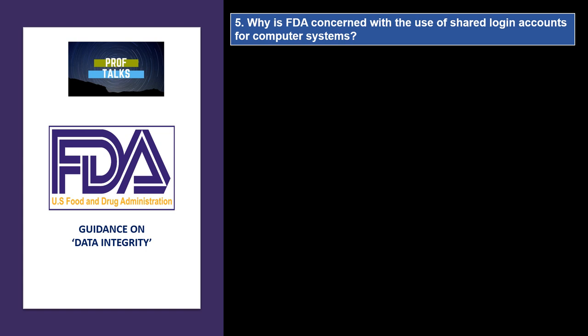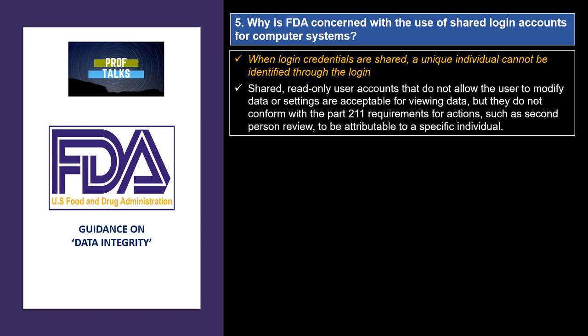The next question is: why is FDA concerned with the use of shared login accounts for computer systems? As seen in the ALCOA definition, attributable means one can find out which person the data is related to. When shared logins are used, the data becomes non-attributable and does not comply with the basic requirement of data integrity, since a unique individual cannot be identified. Shared logins or read-only access are permissible only for viewing data, but these logins cannot be used for data review.